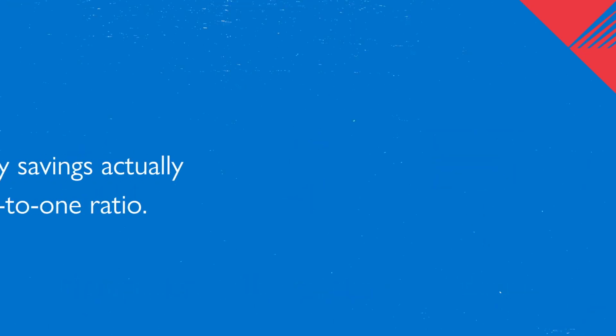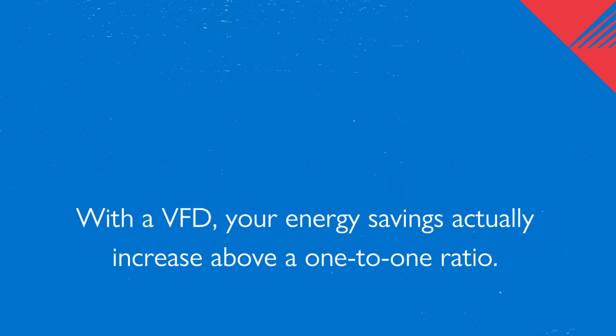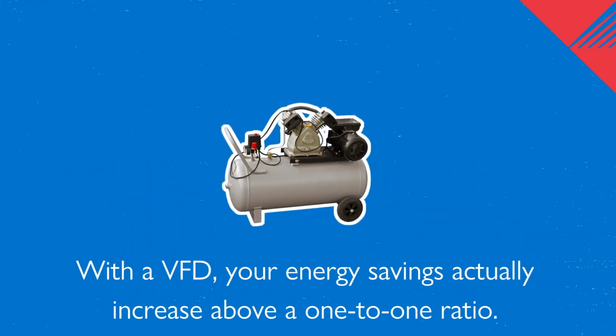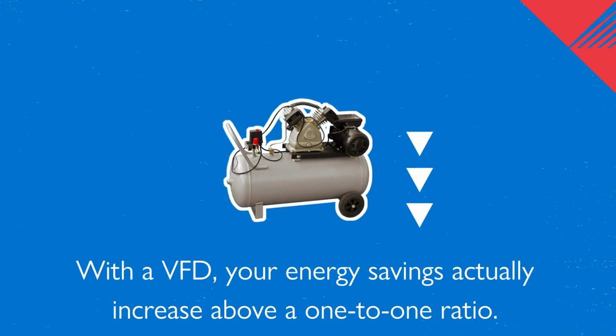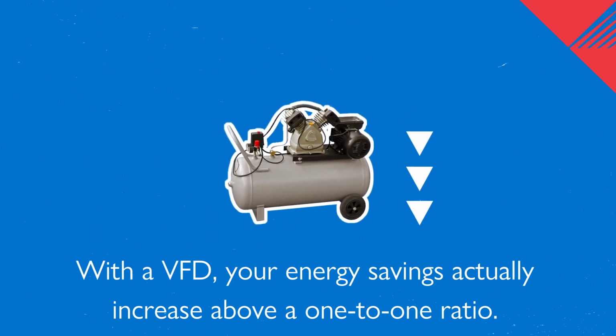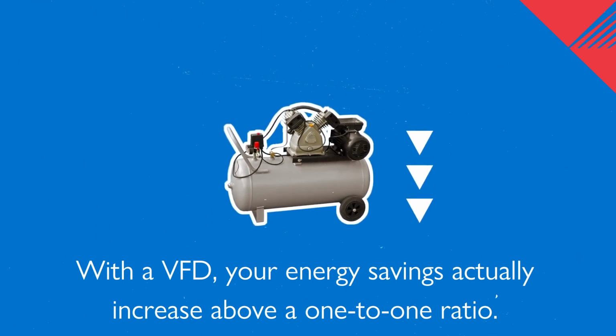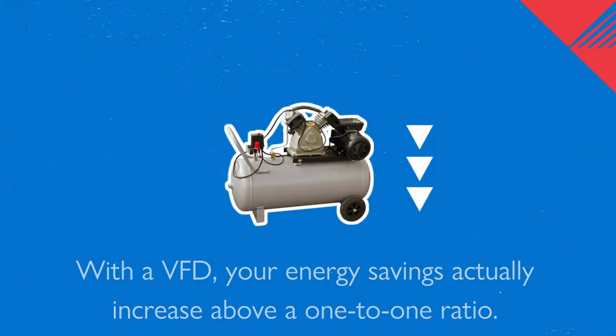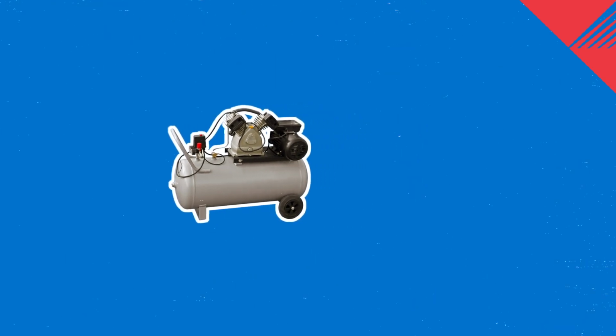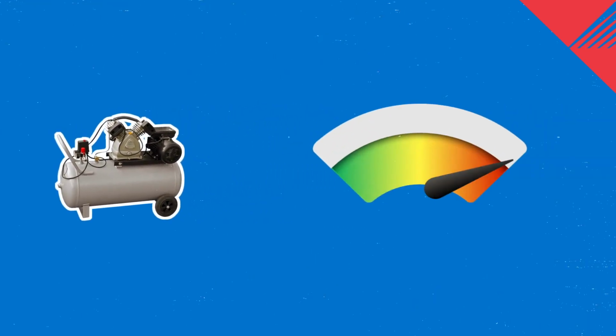In fact, with a VFD, your energy savings actually increase above a 1-to-1 ratio. From a logical standpoint, it's easy to see that if you lower a motor's speed, it draws less energy. But a VFD makes the system even more efficient, so you gain a bonus in energy savings. It actually gets more efficient as it slows the speed down. Let's take a closer look at this concept.